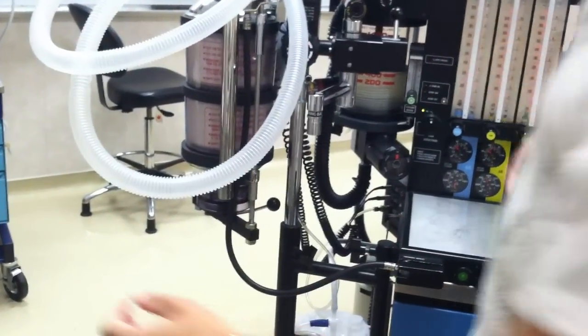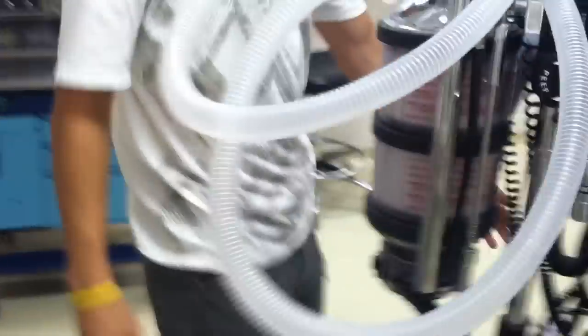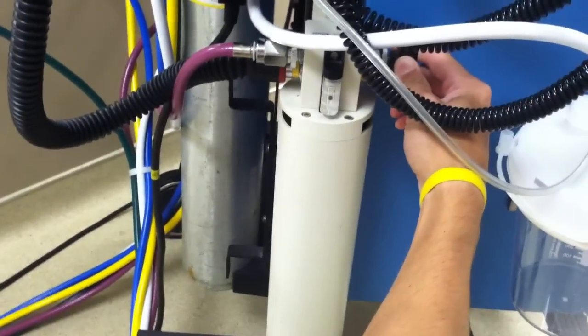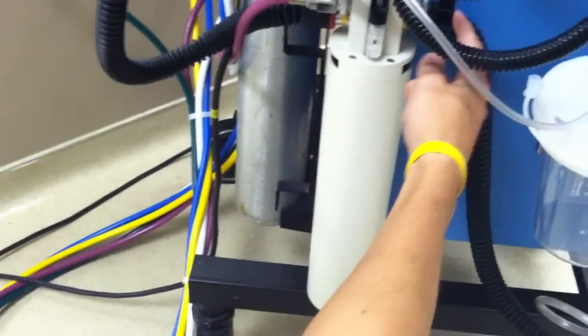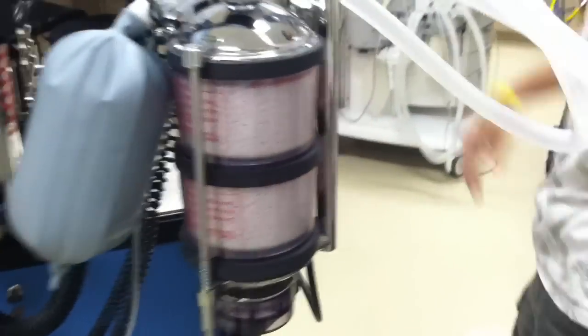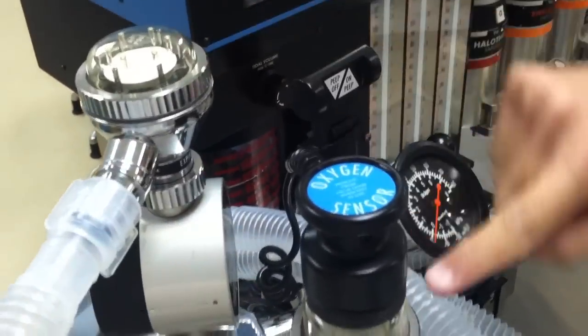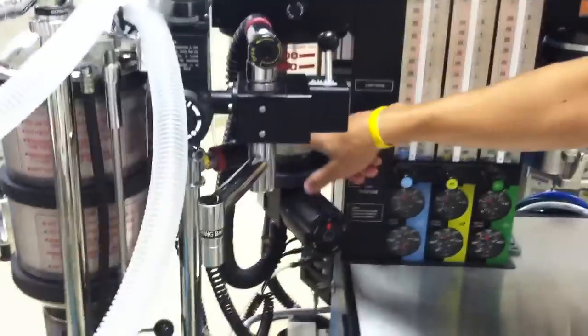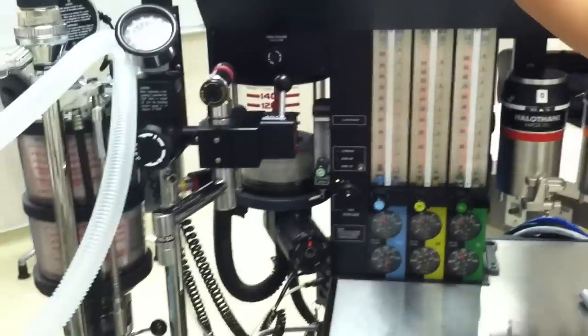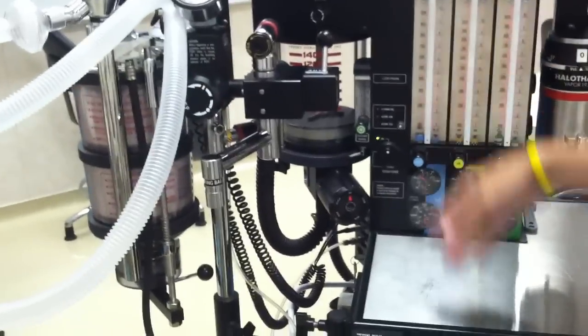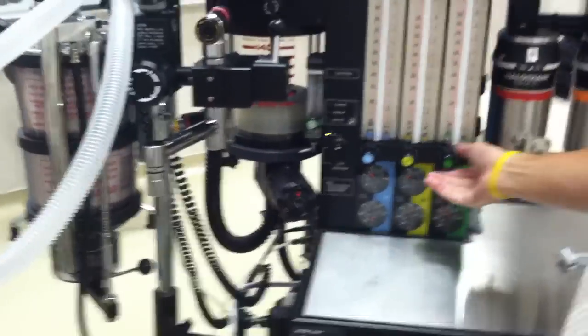While that's kind of doing its thing, I like to come back here and check the scavenging system. Right here, we just need to make sure that that little ball is in the middle of those two lines, and you can control that here. I'm also going to check my CO2 canisters to make sure that that's okay. And I'm going to check my inspiratory and expiratory valves to make sure that they're working, which both of those are. I'd set my tidal volume here. I want to make sure that the machine is getting pretty close to it. It takes a few breaths, but it'll get there.